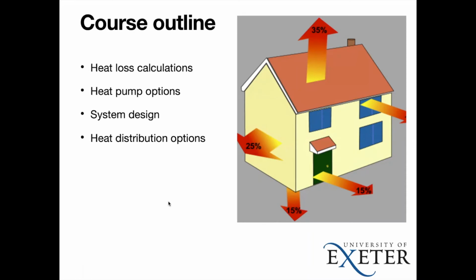Then we're quite keen to highlight the range of heat pump options that are there. So we've done some work looking at mine water as a source of heat pump, lukewarm water, which can really boost the COP of the heat pumps. We've had some funny reactions when we've looked at open source, open loop, river water or spring-fed heat pump systems. They would have been very appropriate for those sites, but the contractors were very cautious of them going forward.